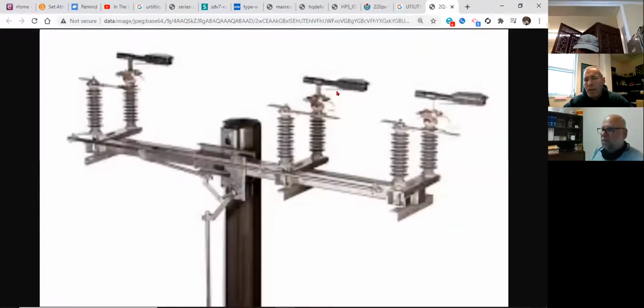Okay, here's my vacuum, my interruption device. That's the jaws of the switch. This blade right here is solid copper. So any time I have a solid copper connection between one side of the switch or the other, that is a dead blade. No fusing capabilities here, no protection at all. It's only used for switching purposes. It's always copper.